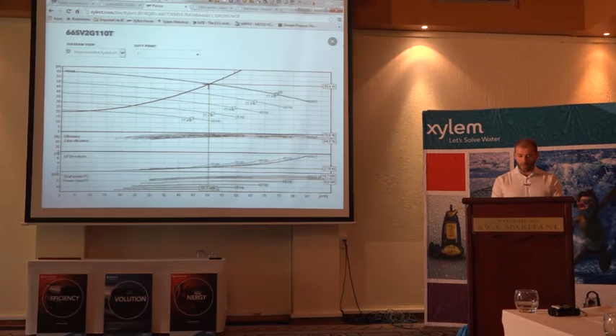Variable speed? Yes. But we didn't select a pump with the variable frequency driver, so it's a fixed speed. But let's see what should happen if we have variable speed. If we look on full screen, we have a better idea. And here we are. Here you have all the curves between 30 and 50 Hertz of the variable frequency driver. So I would say that this pump is working between 28 and 50 Hertz. So, we like this pump.